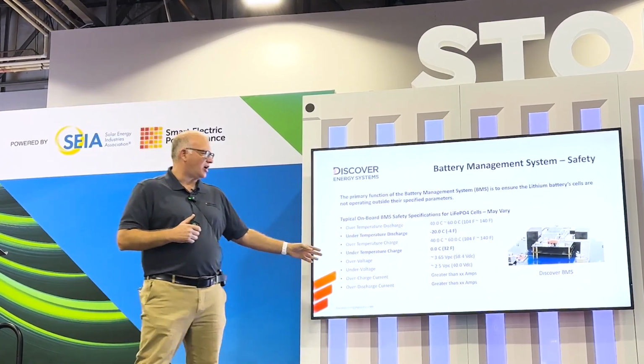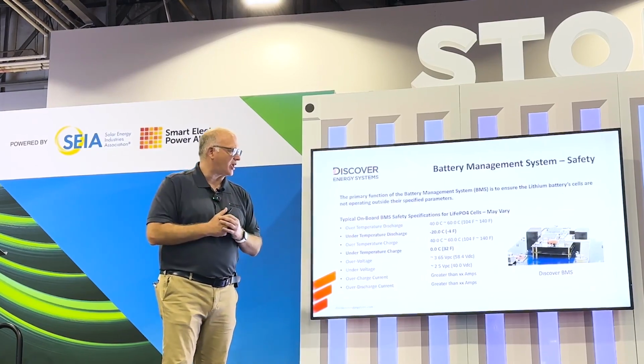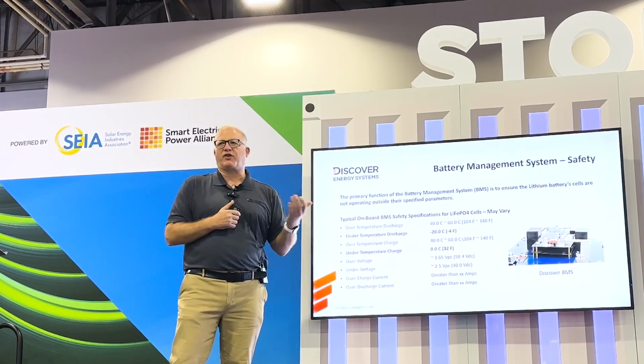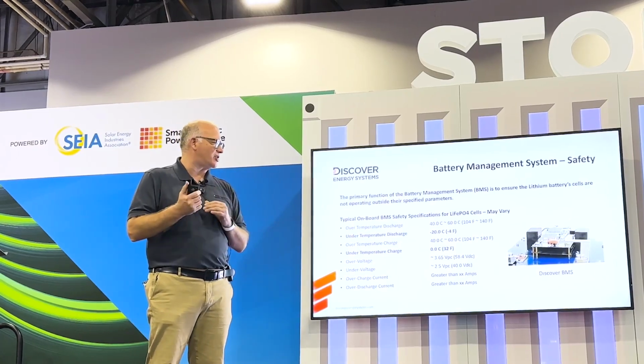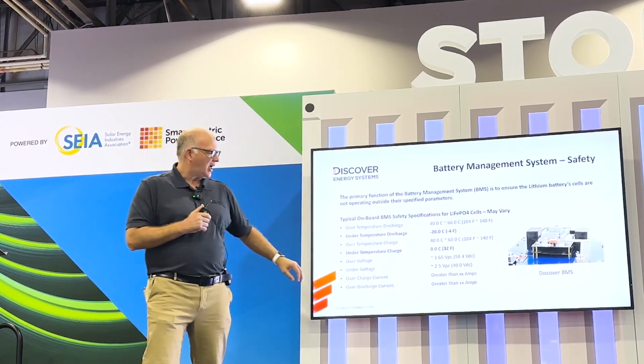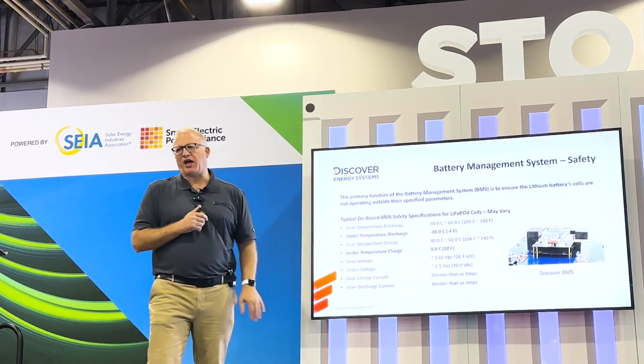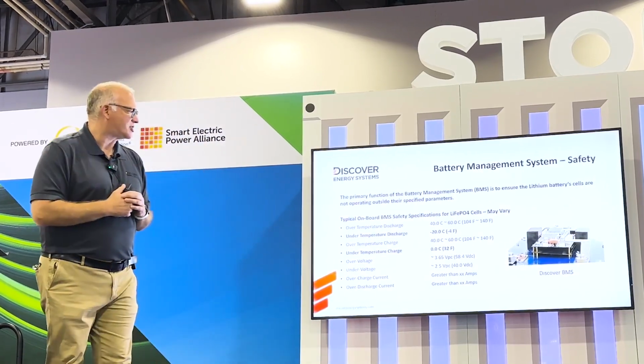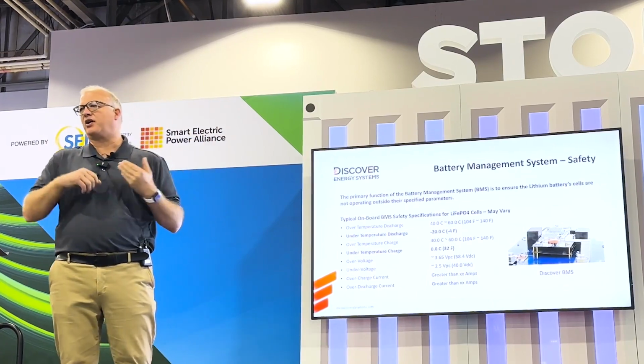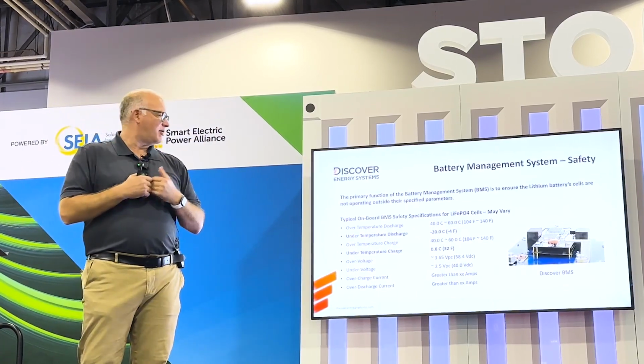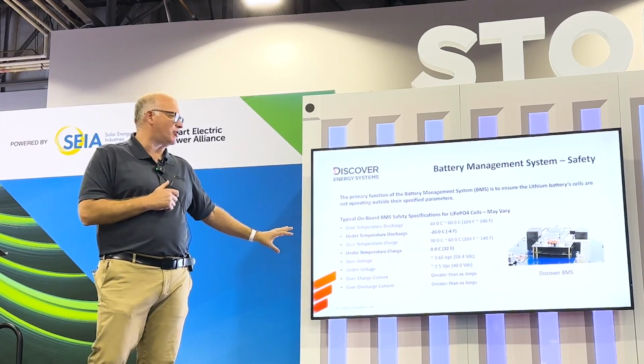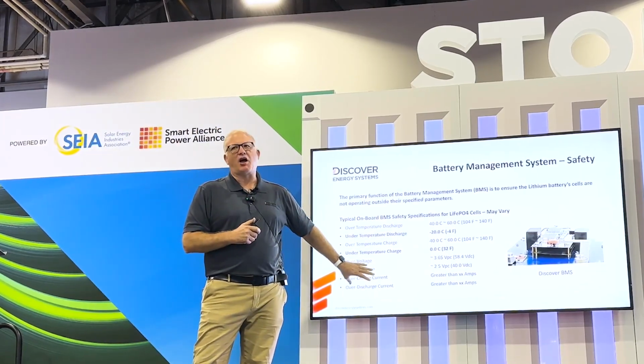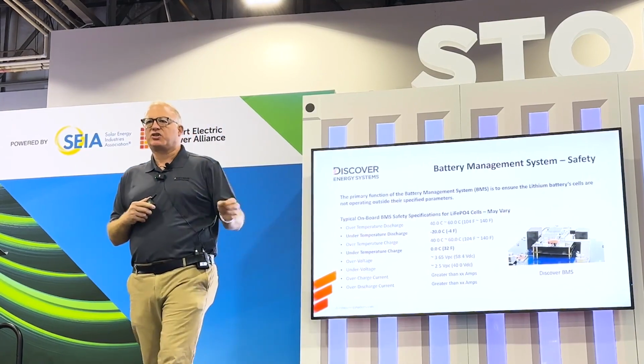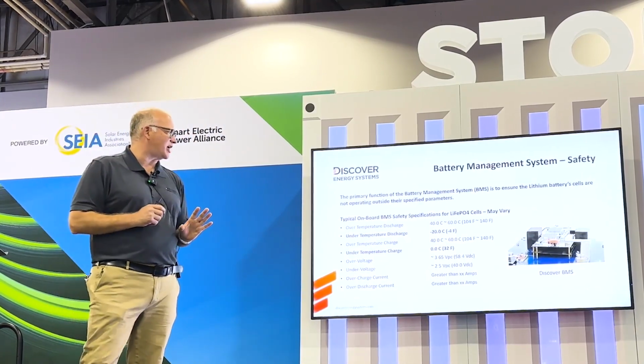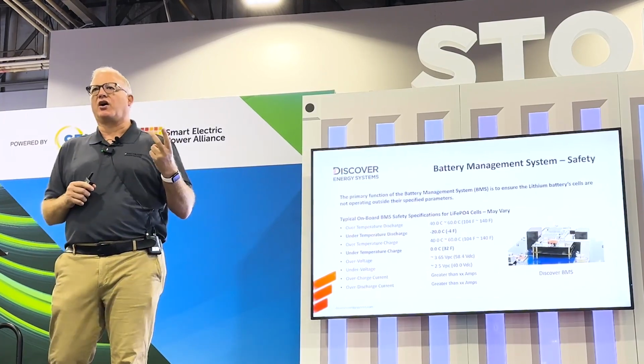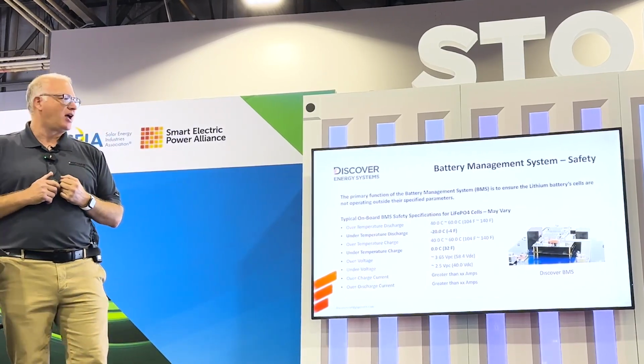Over and under voltage, basically where I'm using 48 volt systems here, it's 3.65 volts per cell. There's some variations on this for a variety of reasons. The other aspect they're looking at is current - so overcharging, overcurrent and undercurrent, which would basically turn the thing off. We're going to look at those more specifically because this is impacted a lot by the battery size, as much as the cells underneath that. So these are the major aspects: temperature, voltage, and current. That's what your BMS is looking at and acting upon.